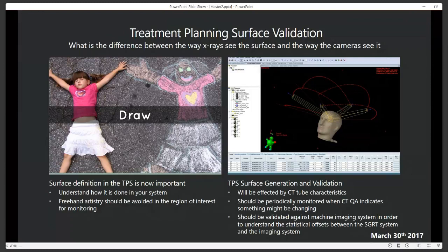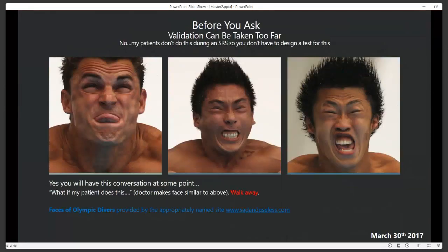Ours are under a millimeter, but they do change with time as your CT tube fatigues and your Hounsfield units drift. So your CT QA and your annual QA is now playing part in your SGRT system QA. Before you ask, validation can be taken way too far. I do not have patients that do this, but you will have this discussion with almost every doctor when doing SRS. If my patient does this and he will make one of these faces, what's going to happen? The appropriate validation step is to walk away, because in all the years I've been doing SRS with SGRT, I've never had a patient actively try to thwart the SGRT system.